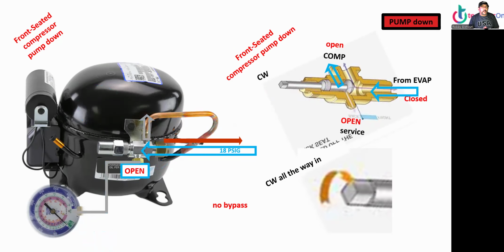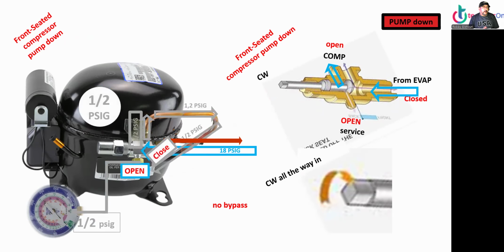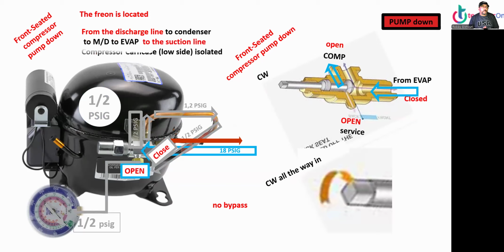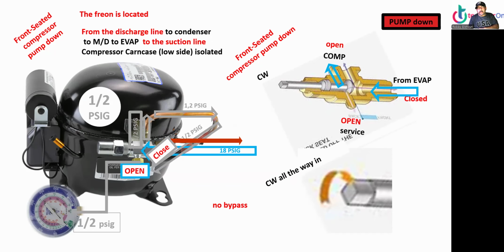Now, front seat, so we can pump down, clockwise all the way. What's going to happen? The compressor is going to pump down and suck all the way to half psig and stop, because it's going to pump from the valve to the compressor. And the Freon is located from the discharge line. Now, the Freon in the system is only from the discharge line all the way to the condenser, to the metering device, evaporator, suction line, and stop at the valve. So inside the compressor is empty, half a psig. All right, Freon from discharge line to metering device, evaporator, suction line. All right, the compressor crankcase, low side, is isolated. But remember, only the crankcase, we still have pressure at the discharge side of the compressor.